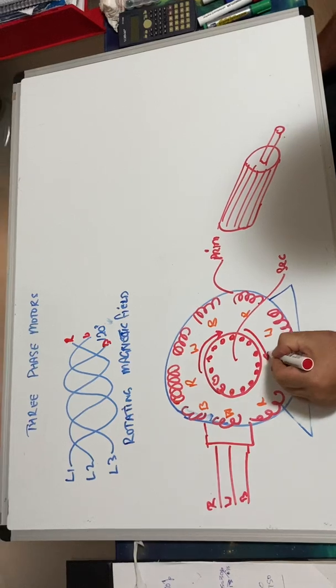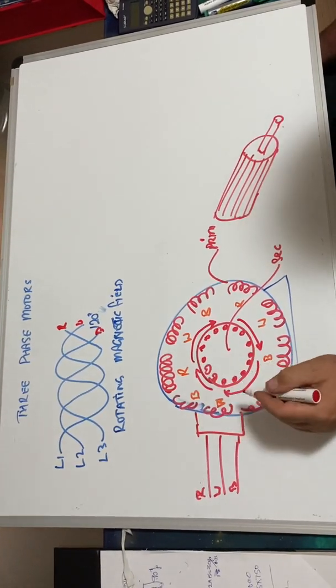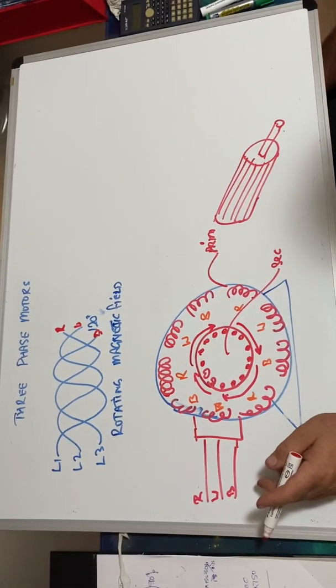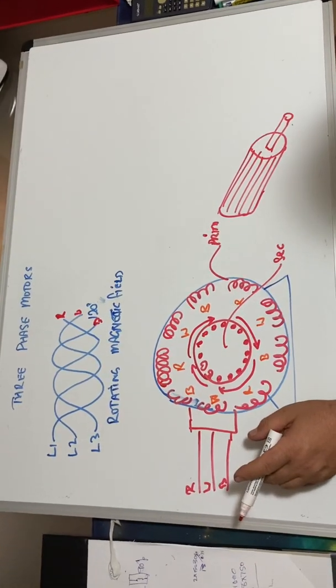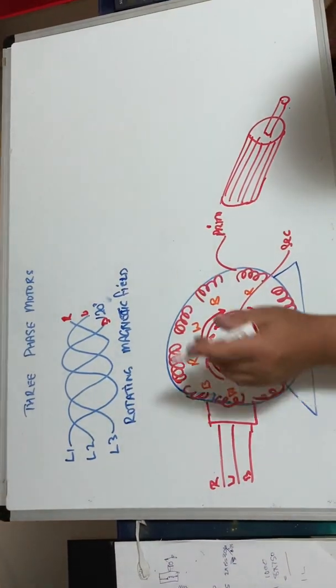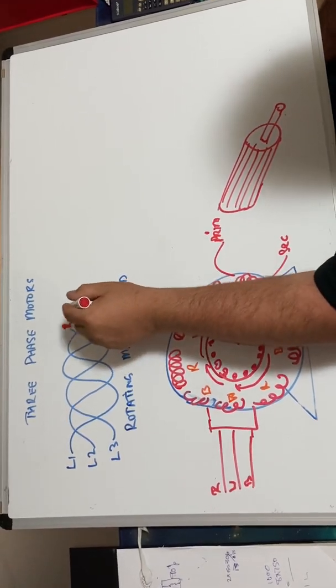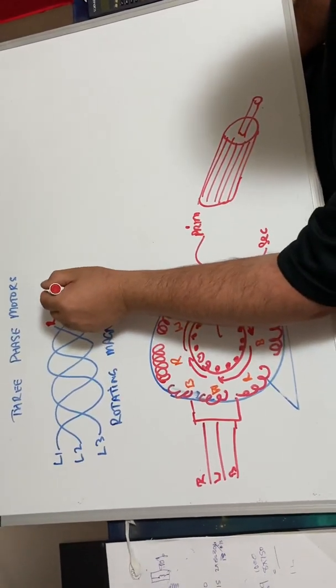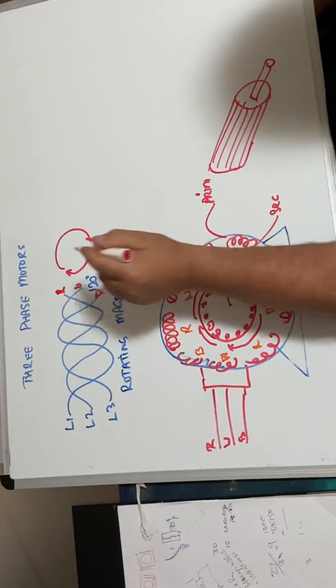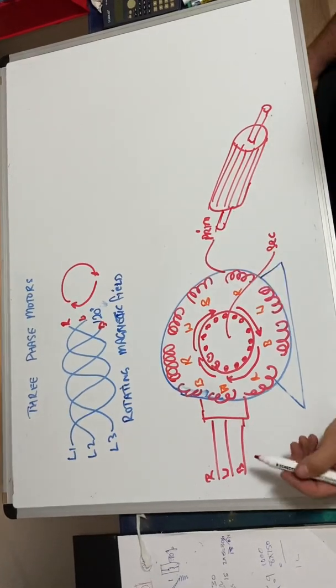As you can see, these red, white, and blue here, they're alternating at different times. We start to get a push and pull effect and this will start to rotate around. Even if I put a coke can or anything in there that can be induced, this will start to rotate. That's why we don't need anything to help start the three-phase motor because it has this rotating magnetic field 120 degrees apart.